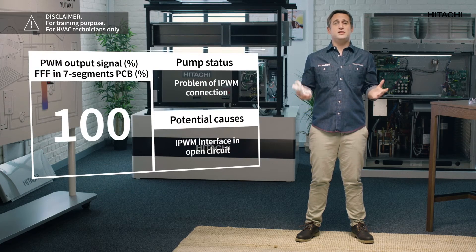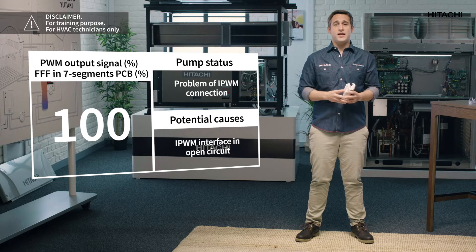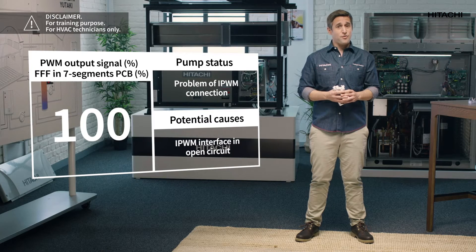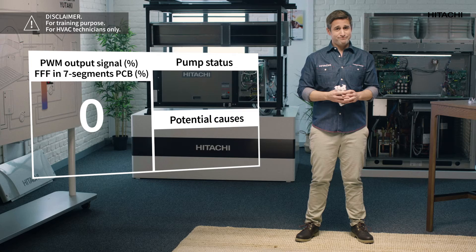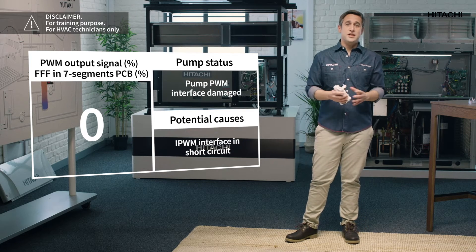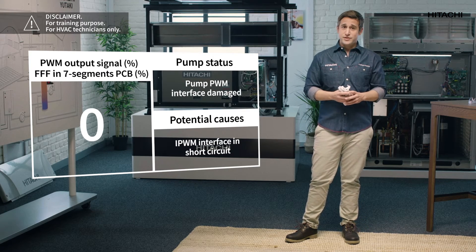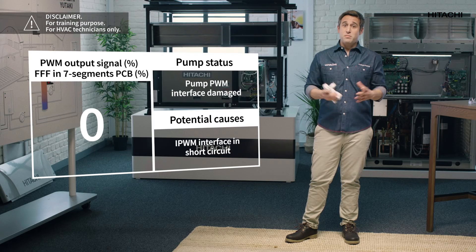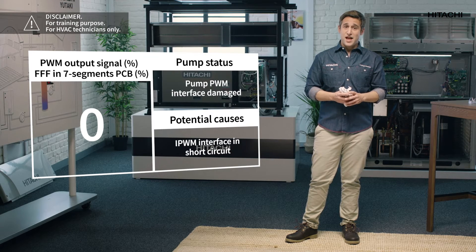A value of 100 is a cause of error, and means that the cable is disconnected — the PCB doesn't receive any signal, and that is why the error appears. A value of 0 is also a cause of error, and means that there is a short circuit — the PCB receives a permanent signal, and that is why the error appears. We may assume that the pump internal circuit is damaged.